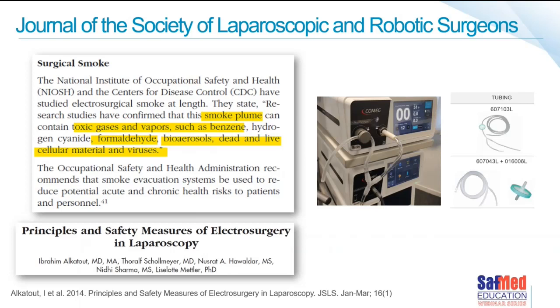Now, of course, the thing to worry about is surgical plume or smoke plume. There is a ton of research and publication on this matter, and I think it's a whole entity unto itself, and one that we haven't grasped yet or taken up well in the South African setting. In America, it is now quite a huge occupational health issue, that of exposure of theatre staff to surgical plume and the ways that we should manage it, including the use of smoke evacuation systems. The surgical plume can contain toxic gases. It contains vapors such as benzene, hydrogen cyanide, formaldehyde, and of course bioaerosols, dead and live cellular material, and viruses. So this kind of thing puts us at risk. So if you're using an insufflator, it really is useful if you have something that's got a filter attached to it, and that would protect both the machine and hopefully the staff as well.